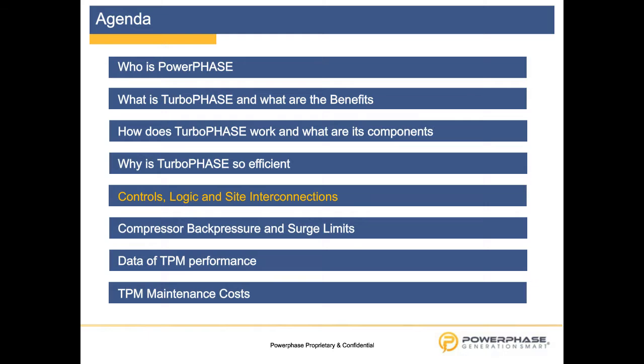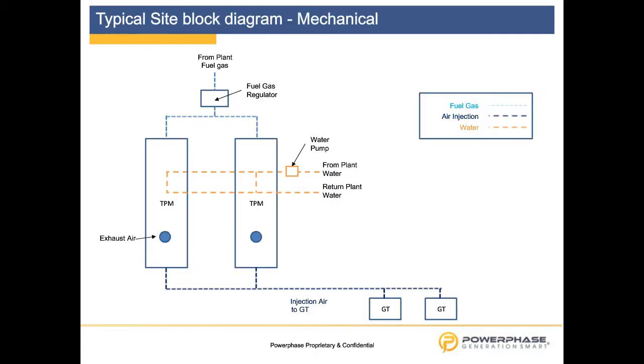Now I'm going to the site interfaces, the interconnections, controls, and logics. We start with a typical mechanical block diagram. To show the scalability here, I have used 2 TPMs. The blue box is in the center of the picture, and this is the delivery scope. We have then a fuel gas regulator. As a standard delivery to our box, we take the plant fuel supply, that is one mechanical interconnection that we need. We take the plant fuel supply in whatever parameters delivered. We reduce it to the required parameters to operate both our boxes. So, then we are with our fuel gas regulating skid.